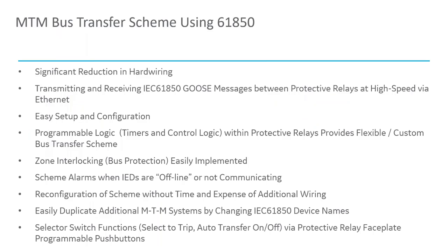The advantages of the main-tie-main scheme include significant wiring reduction, high speed, and constant monitoring of the communication. If a zone interlocking scheme is already implemented, you can easily add the main-tie-main scheme through relay settings, and vice versa. With that, we'll open up for questions.